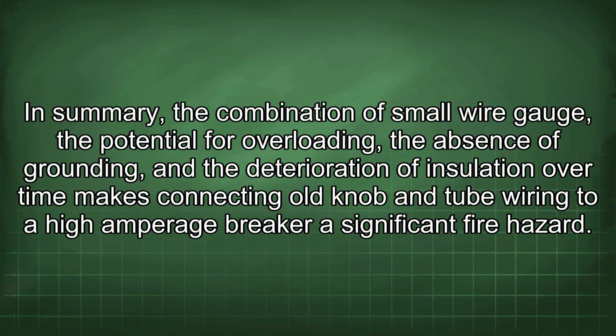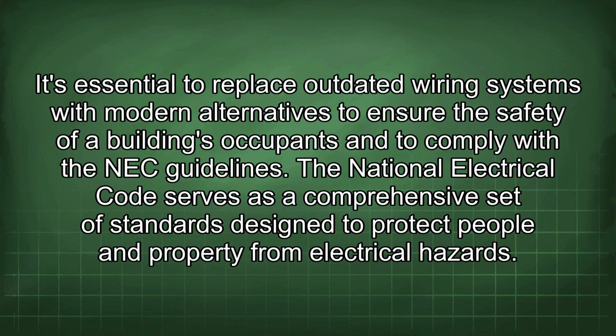In summary, the combination of small wire gauge, the potential for overloading, the absence of grounding, and the deterioration of insulation over time makes connecting old knob and tube wiring to a high amperage breaker a significant fire hazard. It's essential to replace outdated wiring systems with modern alternatives to ensure the safety of a building's occupants and to comply with the NEC guidelines.